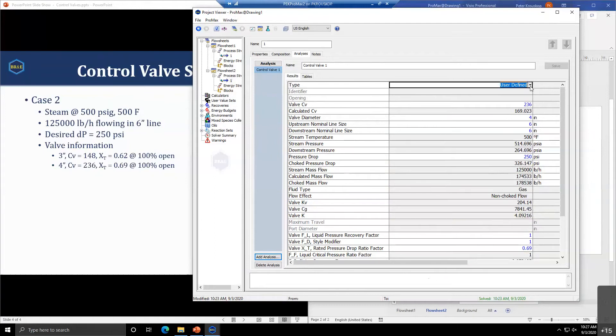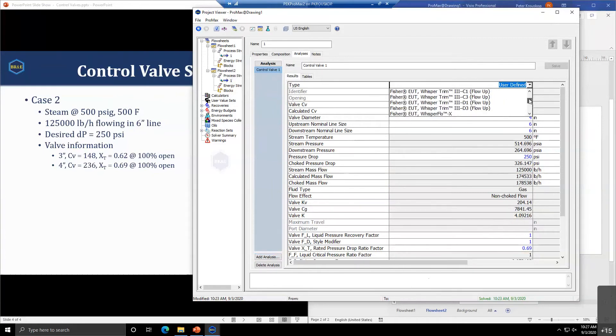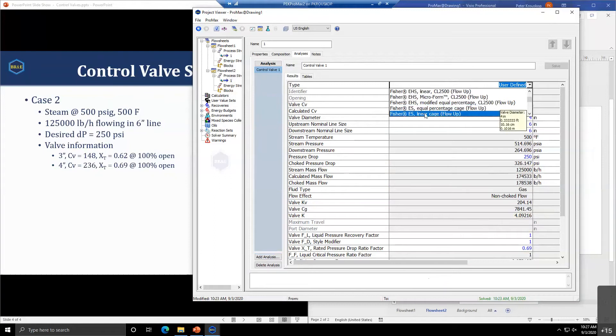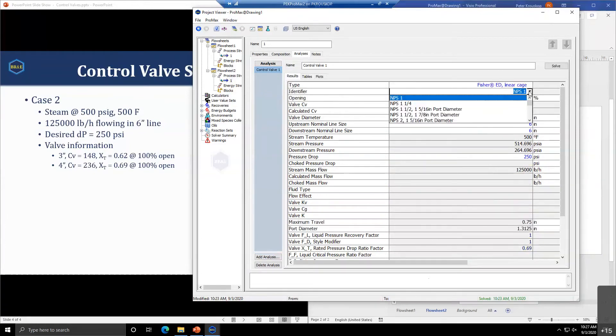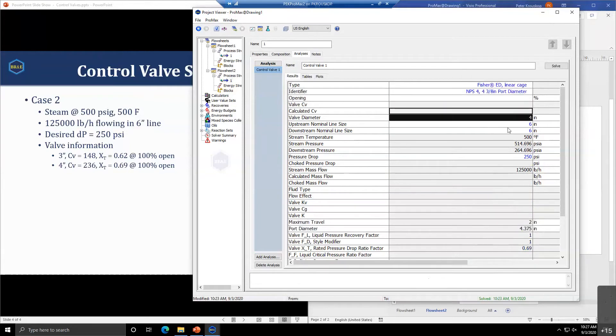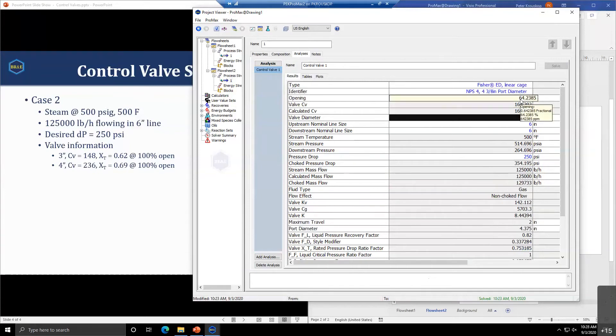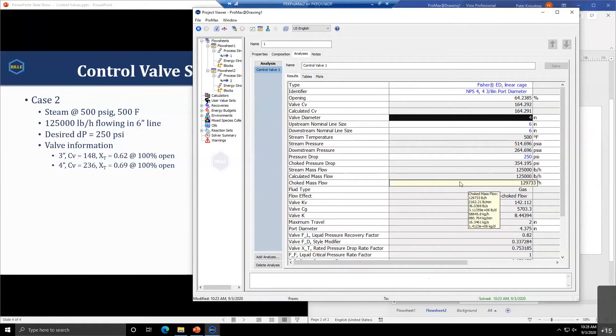We could come in and one of the valves I found that is representative is the ED linear cage. If we go with a 4-inch and solve, that gives us a valve that's going to be 64% open with a CV of 164, allowing our mass flow through at a 250 pound pressure drop.